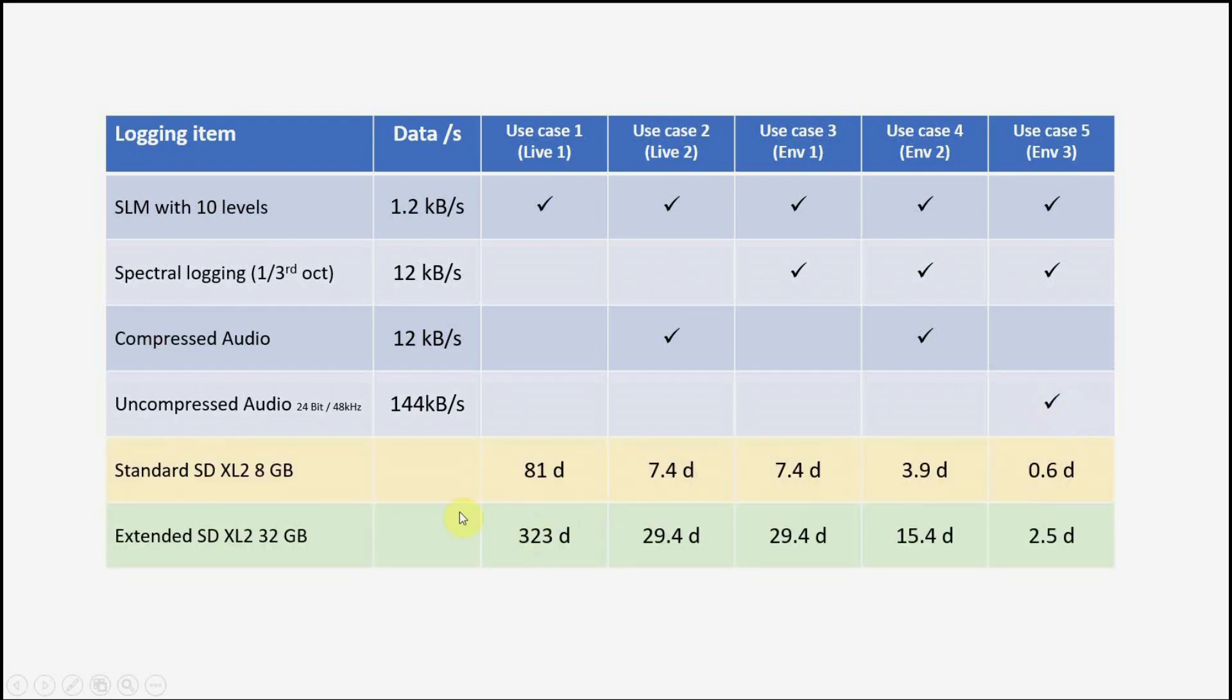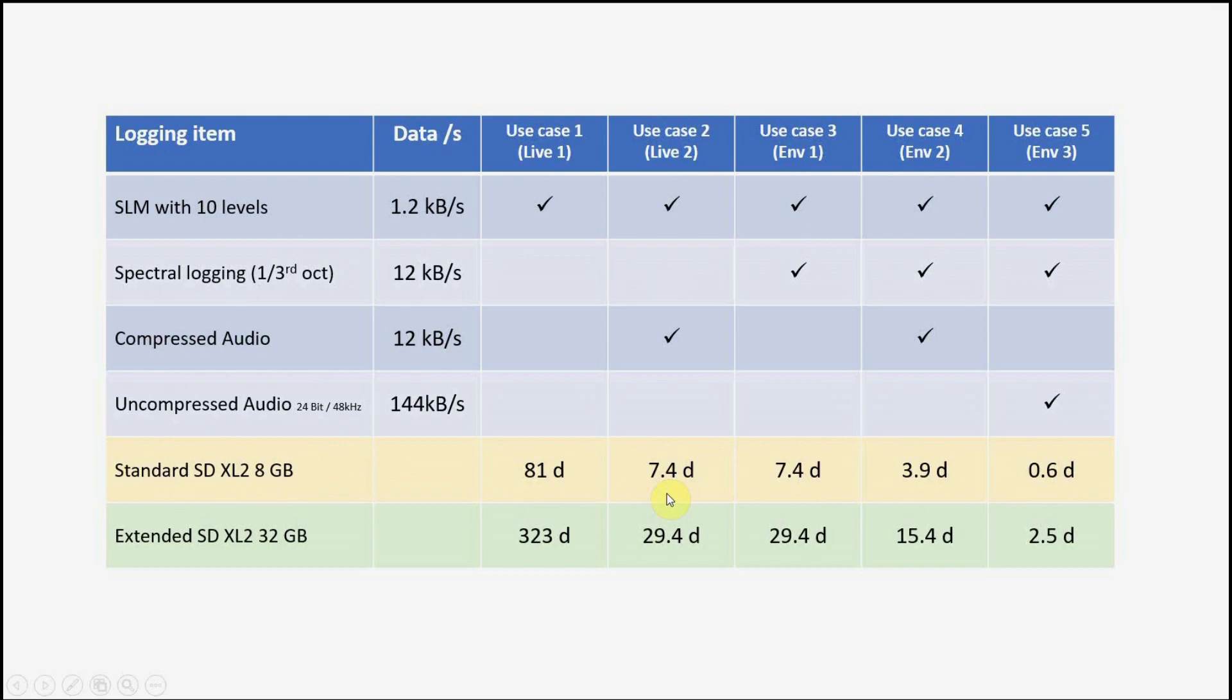If we now look at the memory usage, the standard SD card of XL2 has 8 gigabytes, so we can record here 81 days for live sound wideband values only, seven and a half days if we record also the compressed audio, or for environmental noise analysis with wideband plus spectral information, seven and a half days. And then with compressed audio, four days, and with uncompressed audio, where the usage is higher, 0.6 days can be used.